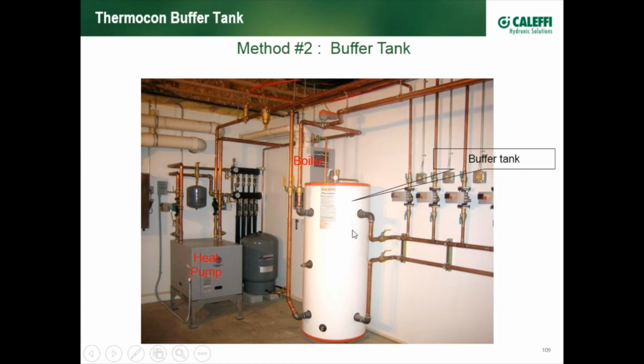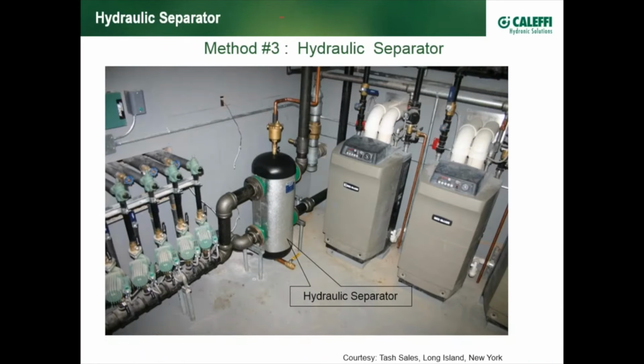So by having a buffer or thermal flywheel, if you will, in addition to hydraulic separation, too frequent contacts of the contactor driving the compressor in the heat pump, and also too frequent on and off actuations of the boiler, are averted, and therefore making the system more reliable and efficient. And the third most quickly growing method, and perhaps now the most common method of hydraulic separation, is using what's called a hydraulic separator, or a hydro separator for short.